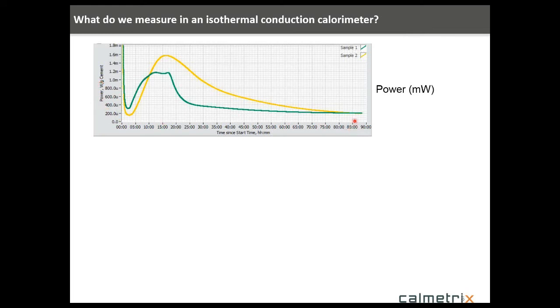And you'll notice here that time is a very long time frame. So it's not unusual to run these experiments for 24, 48, 72, and even longer hours, and maybe sometimes in the order of 30, 40, 50 days. Just depends on the application. There's really no practical limit. There's no limit as far as the instrument is concerned in terms of the length of the experiment. It's really going to be more associated with the type of experiment that you're doing and the absolute signal relative to the baseline and so forth.